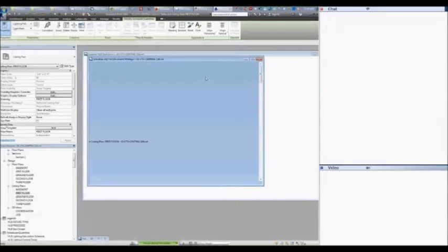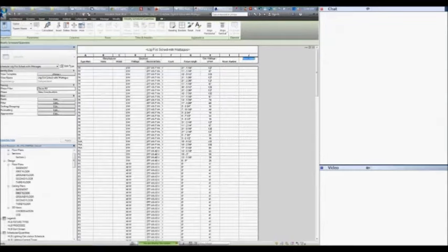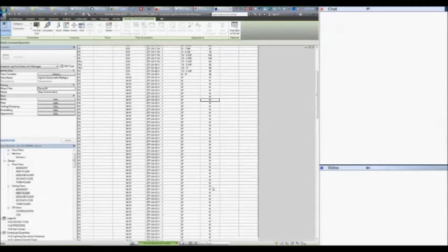So if I go to the lighting fixture schedule, you can see the P1, which is the linear fixture, and the P1A, which is a variant. They're reporting their fixture length. Then there's a calculation field, which works out what the wattage is. For P3s, you can see its report length as 0, and so as a result, it knows to just take the wattage, not to multiply the wattage by the length.